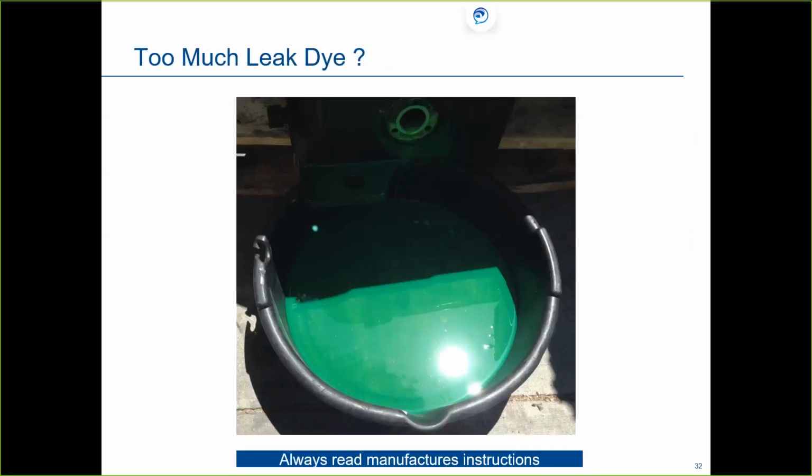On the average, if we have 10 compressors we're tearing down in Denver, Colorado, or San Antonio, Texas, 7 of those will probably have dye in them at some level. Small trace to something like this. I've seen this more times than I can count.